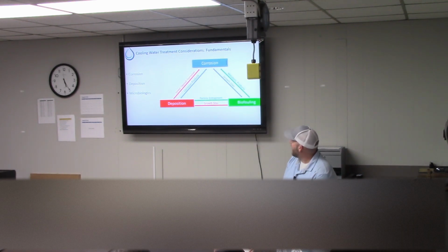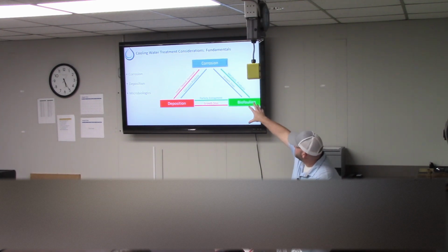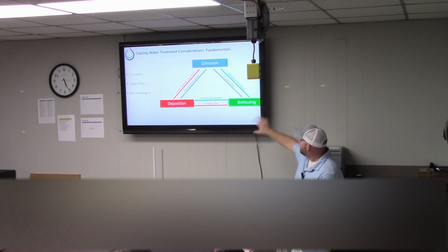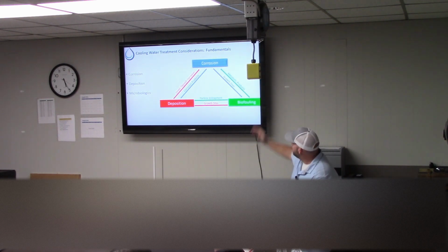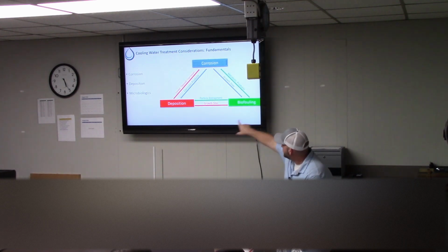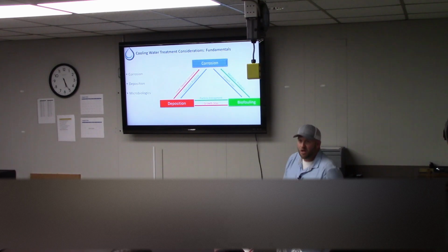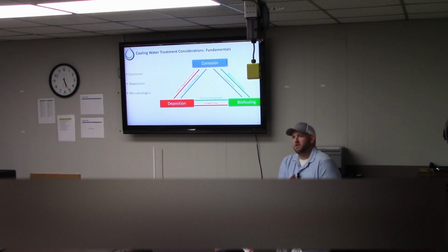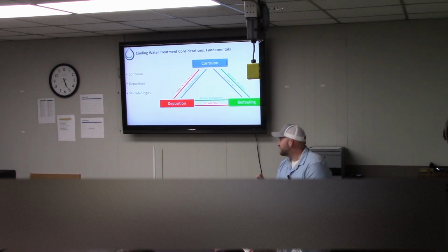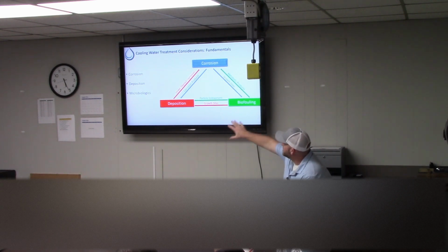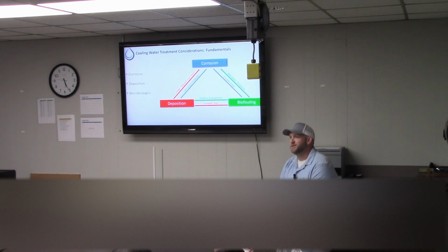Corrosion, deposition, and microbiome. In my mind, amongst all the voices talking, this is how I see cooling tower treatment. And I want to point out the interdependent relationship between all of the three. When you look at it, biofouling can lead to deposition, it can lead to corrosion, just the same way that deposition could lead to biofouling, or it could lead to corrosion. What does this tell us? What this should communicate to us is that you cannot partially treat a cooling water system. You're either in it or you ain't. So if we're not doing something to address biofouling, deposition, and corrosion, we're truly doing ourselves a disservice.